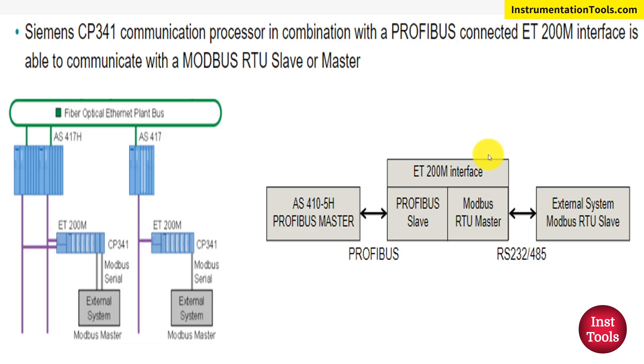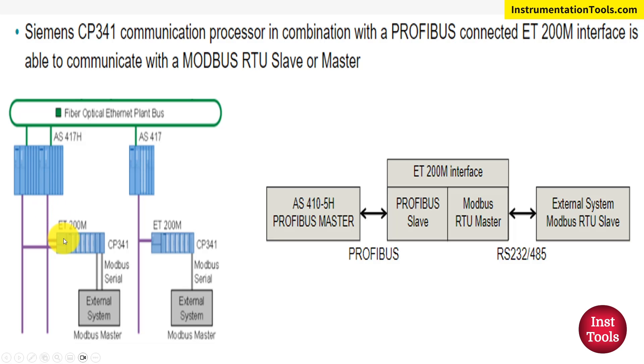In Siemens, there is a special communication processor card called CP341. It combines with Profibus connected to an ET200M interface. As we discussed in the last video, this will be termed as PlantBus. Lines shown in green color indicate ProfiNet, and lines shown in purple color indicate Profibus connections. As you can see, ET200M or remote I/O is established in the automation architecture.